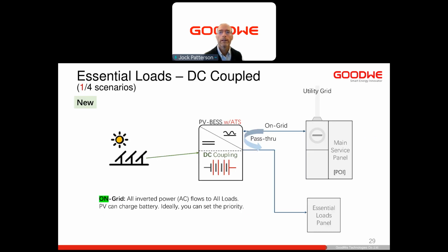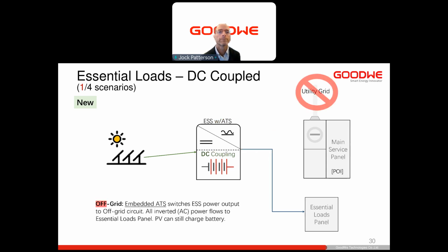What we have here is an ESS in the center, receiving power from an array that's connected to the main service panel. And we have an essential loads panel. The power from the grid can come into the main service panel and pass through on the on-grid circuit to the ESS inverter, where it then can be passed through further to the essential loads panel. So that's how power moves to the essential loads panel when you're on grid. When we go off grid, then it's only our PV and battery providing power to the essential loads panel. The switch to turn off the on-grid connection is embedded in this ESS.